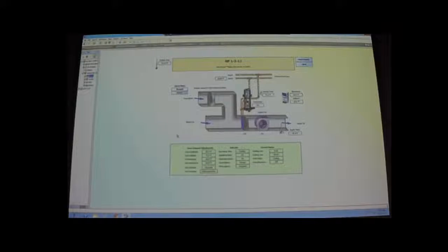But you reset this unit, and the space temperature would be like 77 degrees. And you reset this unit, the unit turns back on, and the space temperature instantly almost starts dropping down into the low 60s. So it's almost like there's just so many air exchanges in this room, and then it thinks that it's too cold, and it shifts back into heating mode, and kind of does this little tail wagging the dog. I think that's one of the ones that's on our list.